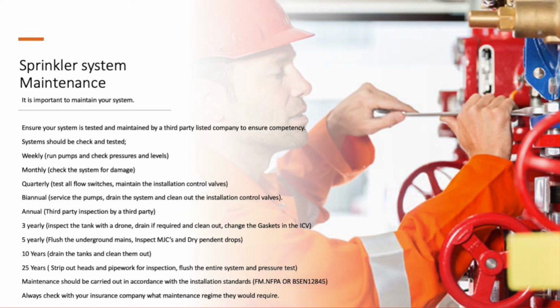Systems should be checked and tested. So on a weekly basis, pumps should be run, pressure should be checked, and levels should be checked. Monthly, check the system for damage, also run your weekly tests. Quarterly, you need to do the weekly and monthly stuff. You test all your flow switches and pressure switches and maintain the installation control valve. So that means basically opening it up, giving it a good look, cleaning it if possible.